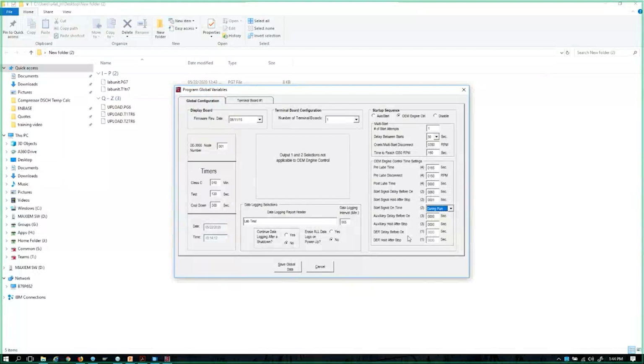And then the last one is output module 1, and we refer to this as driven equipment ready, delay before on, and driven equipment ready, hold after stop. Now, this will work the same way whether we're dealing with a Waukesha or a Caterpillar engine or any other OEM system, but we do not let you change this. So we have 0 seconds on, 0 seconds off. This is the key, most critical factor of how we're going to make sure this unit shuts down.